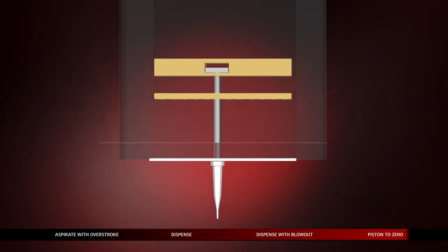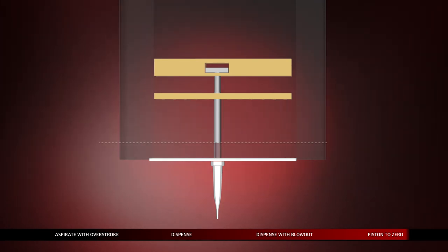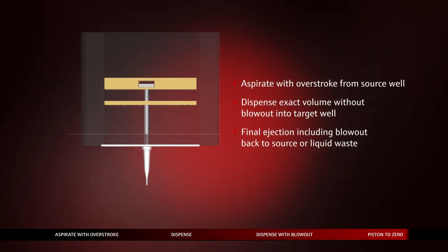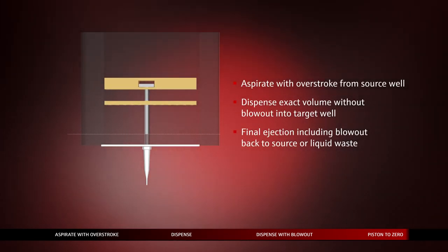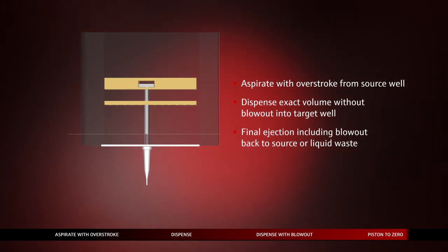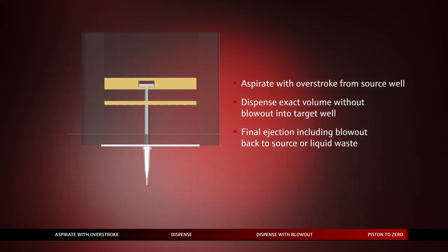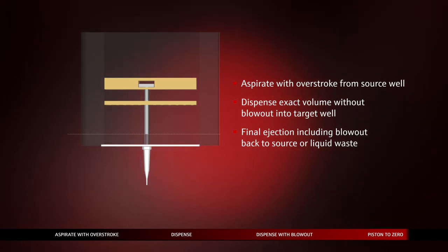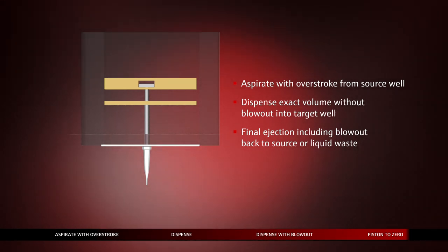To summarize, reverse pipetting is aspirate with overstroke from a source well and dispense the exact volume without blowout. Final ejection includes blowout volume back to source or into the liquid waste.